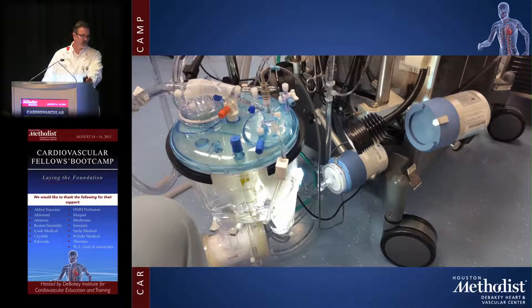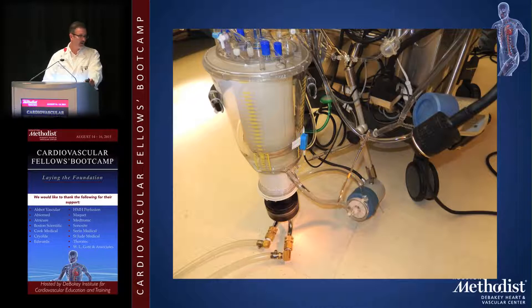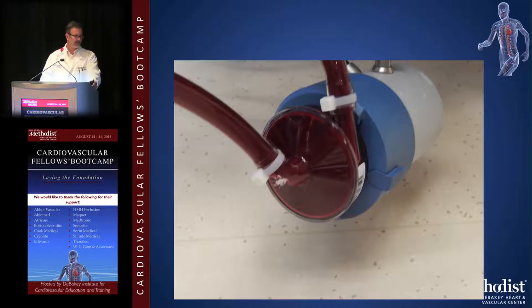Here's a picture of the pump setup — the pump is here with a light on the reservoir. The venous cannula comes in and fills the reservoir, which then fills the pump. The perfusionist is always watching the reservoir level because if it drops too low you'll suck air. The heat exchanger is visible here, and the pump is the lowest component on the entire apparatus, as it fills by gravity.